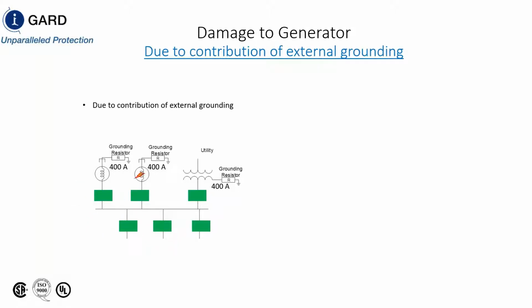But hybrid high resistance grounding was developed for when you have a fault internally to the stator fault winding. So you can see a fault right there. We still have the 3 parallel sources when you have a ground fault inside the stator fault winding. So there are 3 sources. You open up the breaker because the differential protection is going to pick up that ground fault, specifically on medium voltage bus connected generators, and isolate that fault within 100 milliseconds. 1 cycle to detect the fault, 5 cycles for the breaker to open if you have a 5-cycle breaker.